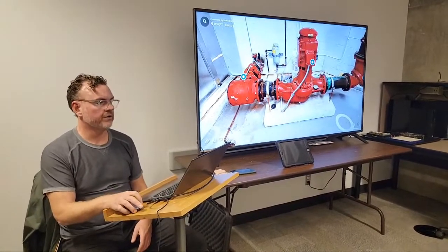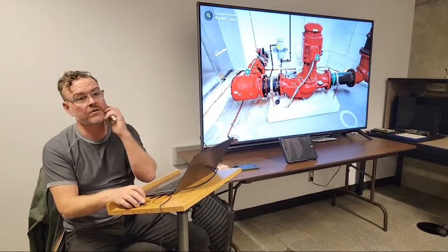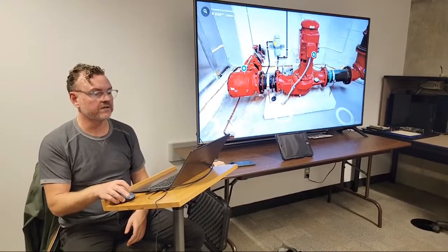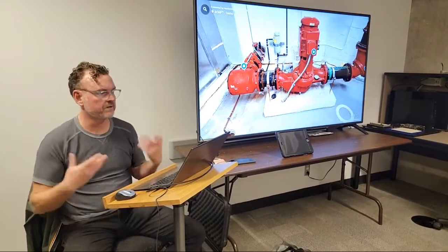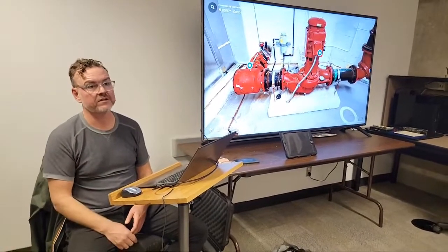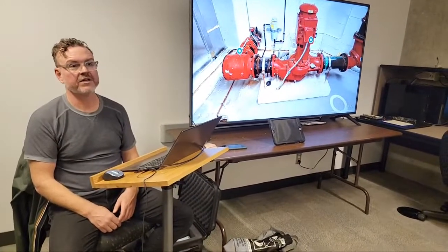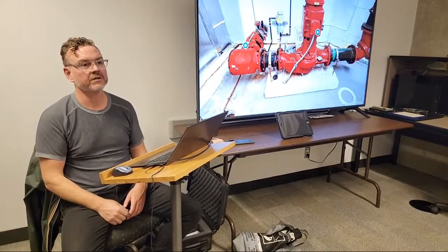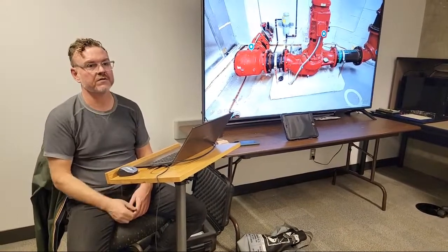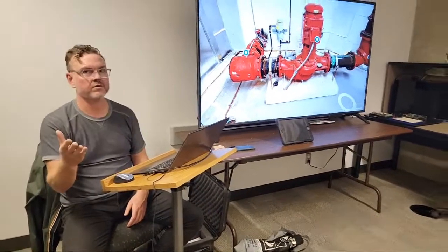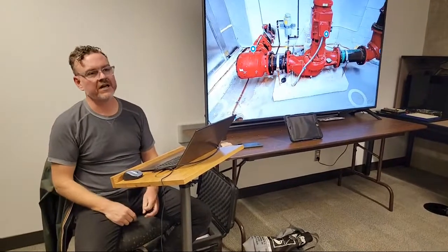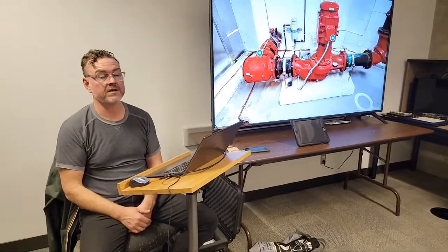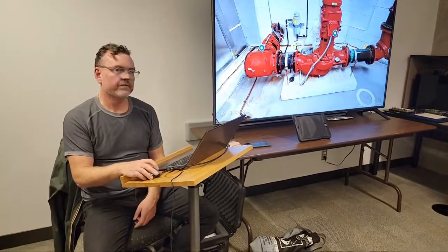So, to your question about the difference between going to site versus having it in VR, one of the reasons why I started looking at this, aside from the documentation missing, was I went and looked at 5 buildings, about 3 hours away, and I wish I had taken just 4 more 2D pictures, because I was looking for a valve that wasn't there, but I was in the wrong building. I was looking for a summer winter changeover, when it switches from boiler heating into chiller cooling, but after an hour of scratching my head, I realized that it was heating only in the building. So there's no air conditioning in the building.